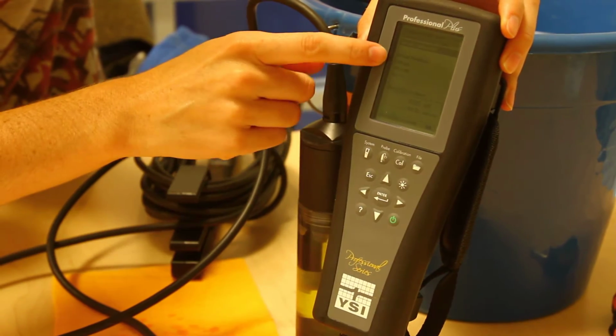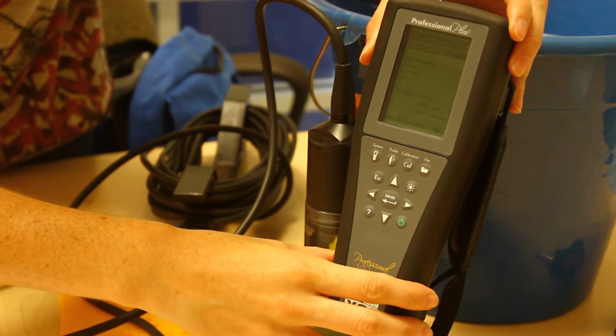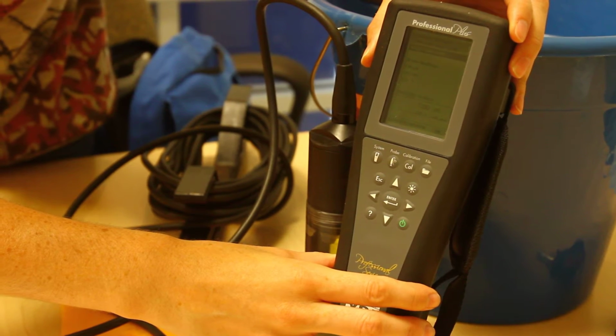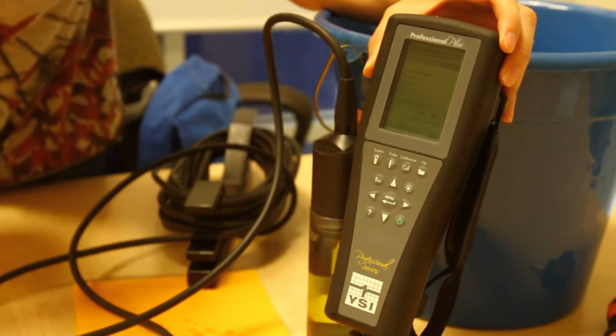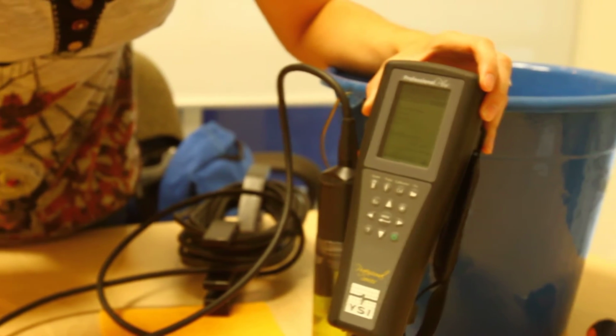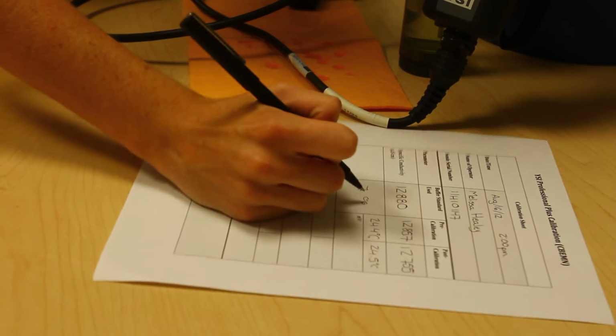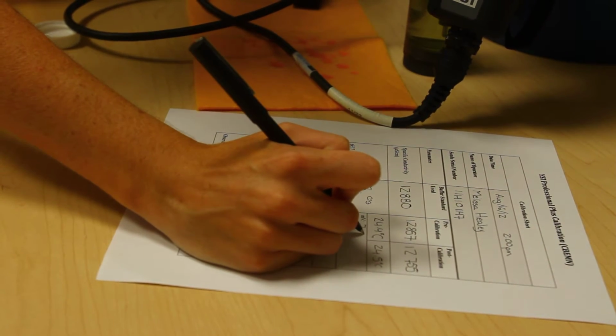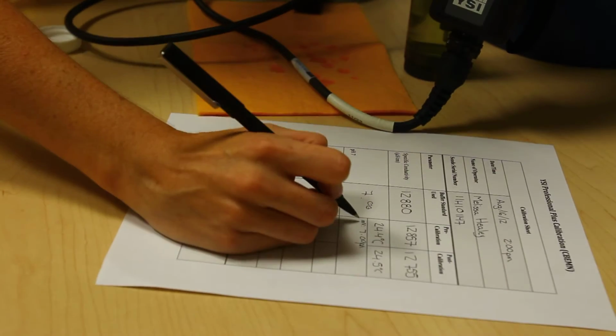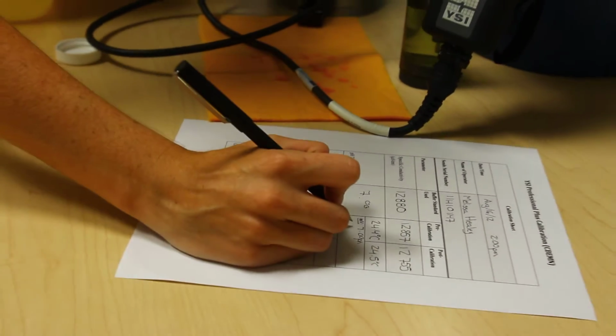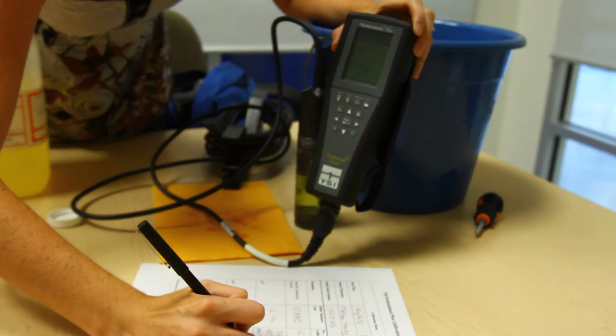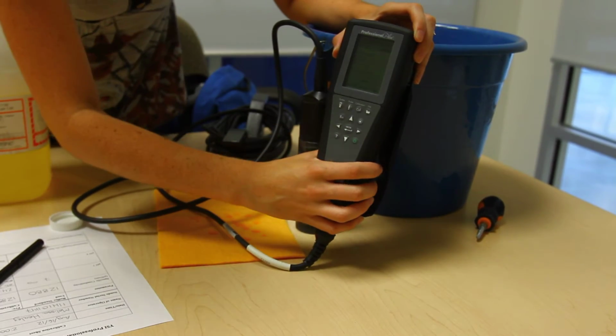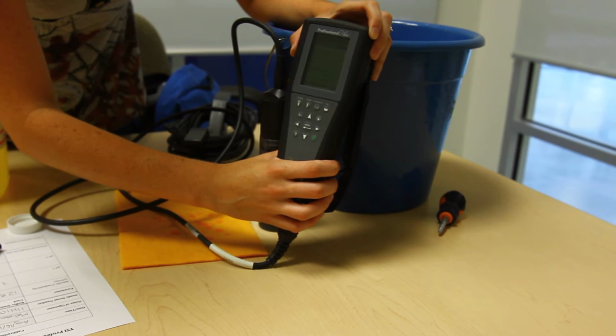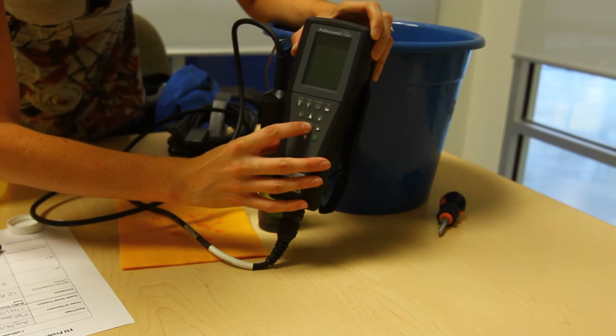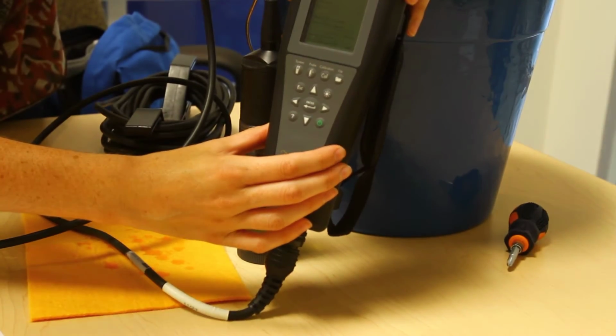Observe the pH reading, and when the values stabilize with no significant change for approximately 30 seconds, record the pH value as well as the millivolt value in your pre-calibration section in your calibration sheet. Scroll to Accept Calibration and press Enter. You can now begin for your next buffer.